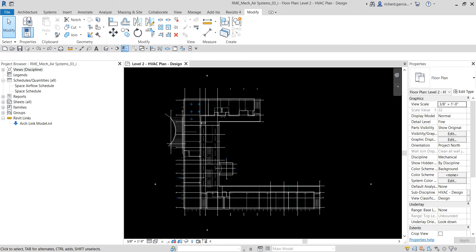This workflow is the Revit MEP recommended best practice for systems creation. In this exercise we are also going to use the system browser to validate the systems. Take note that unlike logical connections, physical connections like ductwork are not required for system designing — however, they are necessary to perform calculations such as sizing that reference the physical geometry.